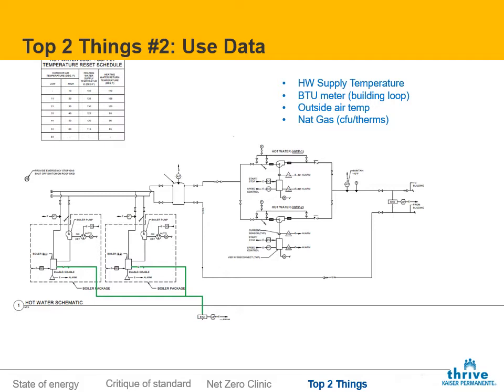Column number 1 would be a timestamp, and then column number 2 would be the supply water temperature set point. And column number 3 would be the actual supply water temperature, and then you'd have GPM and return water temperature, and then the last column in the data set would be the natural gas volume. That's all the data that you need to validate the system design. And you'd validate the system design like this.